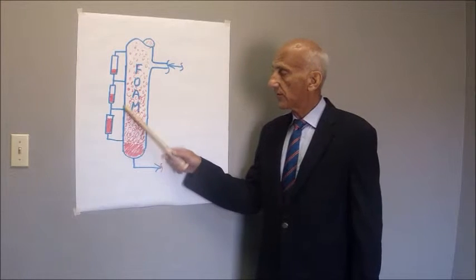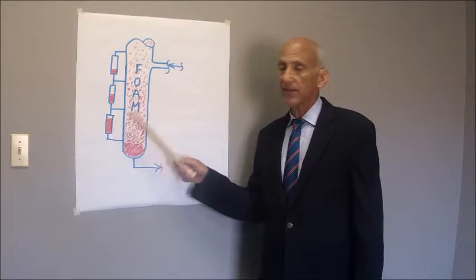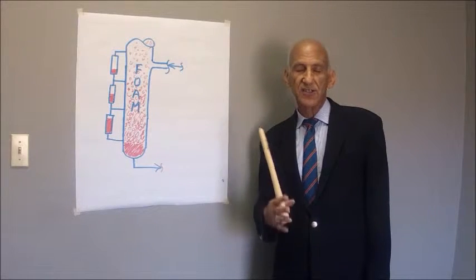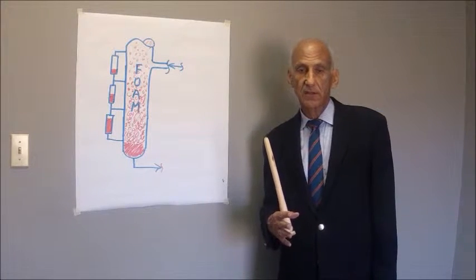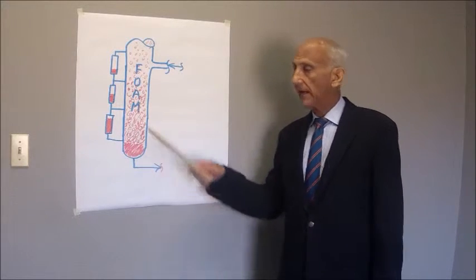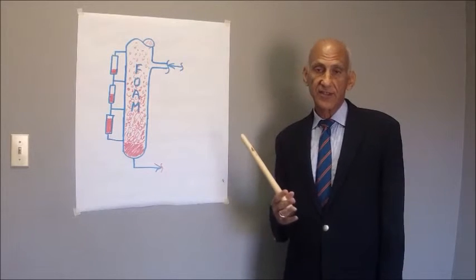And again, the only reason we see a level at all is because the density of the foam is less dense than the density of the clear liquid between the taps. And the lighter foam has a lower density.